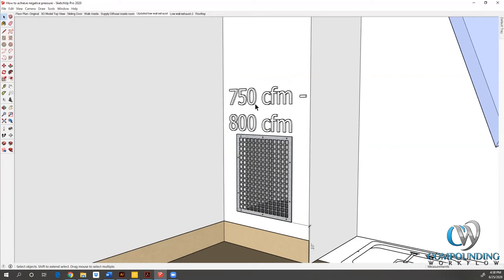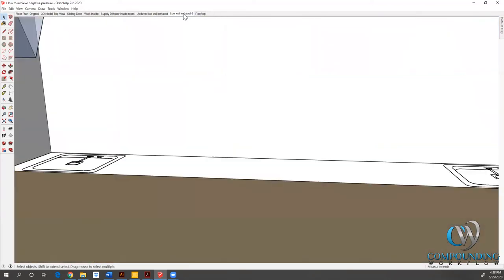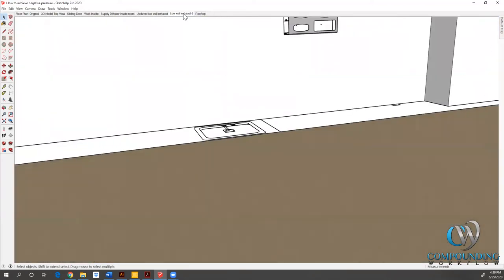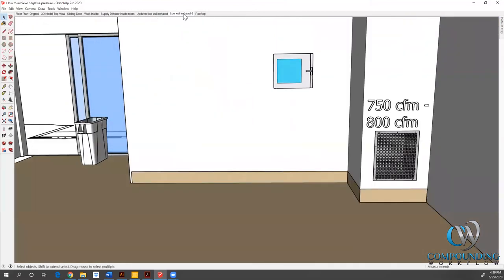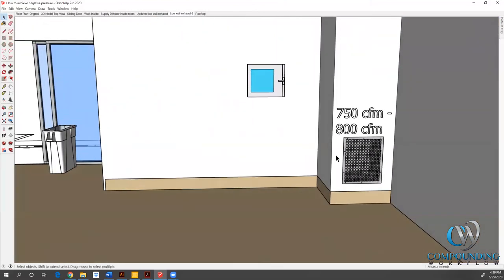I'll show you a makeup air unit in just a moment. So another 15 to 20 to 25% above that is about 1600 CFM. So 750 here or 800, this is kind of like a low or a medium or whatever that number, the test and balance company will actually back into this number. These are approximate numbers that we give to the engineers or the HVAC people so they know what they're working with, because the duct sizing is all contingent on how much air and at what pressure we're going to move through.